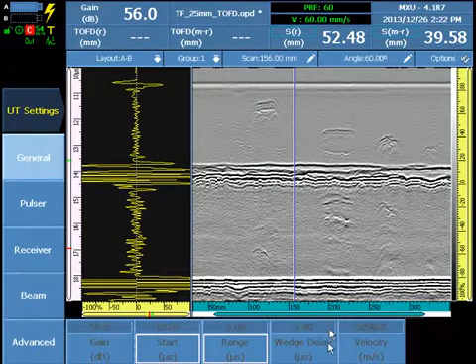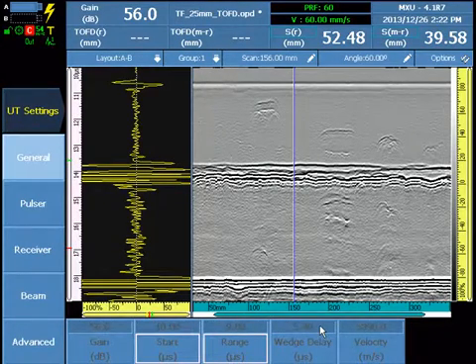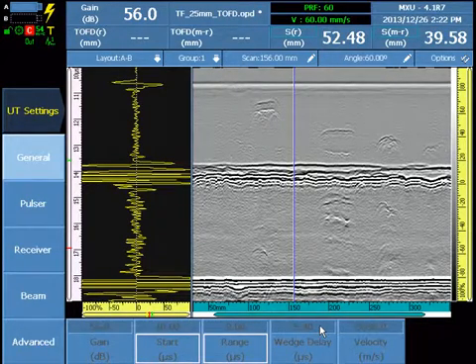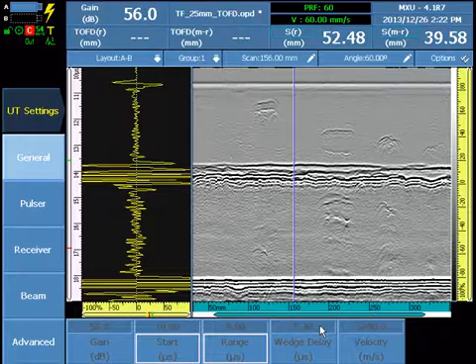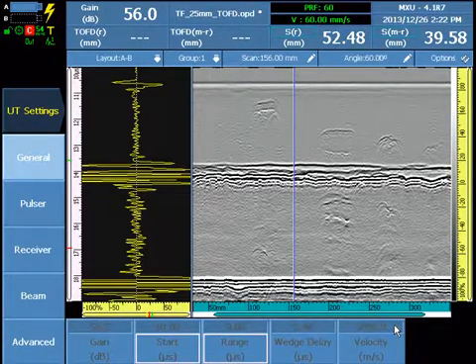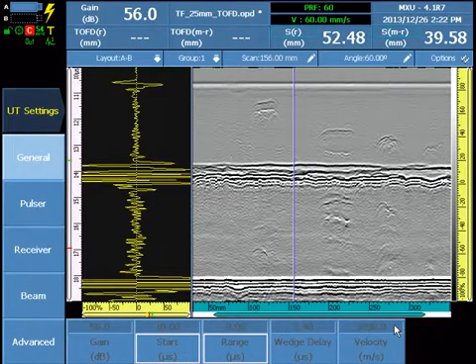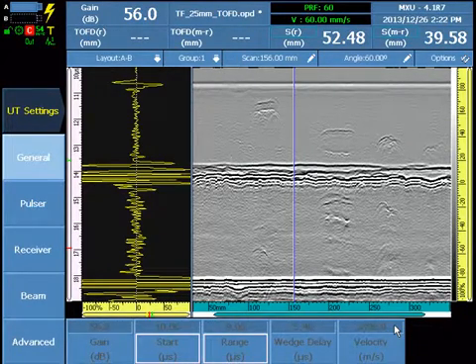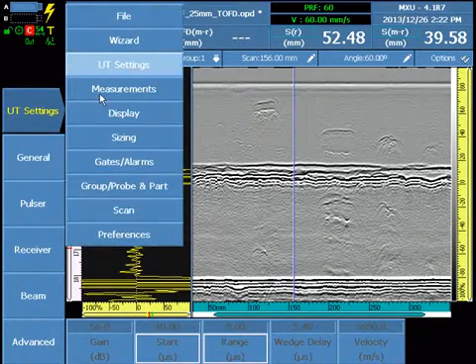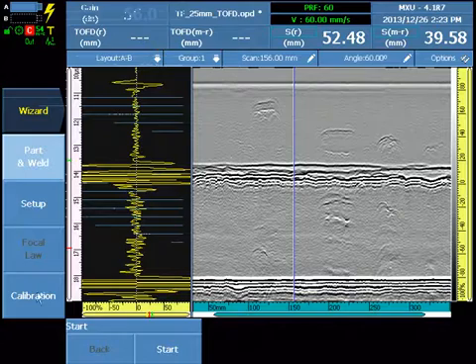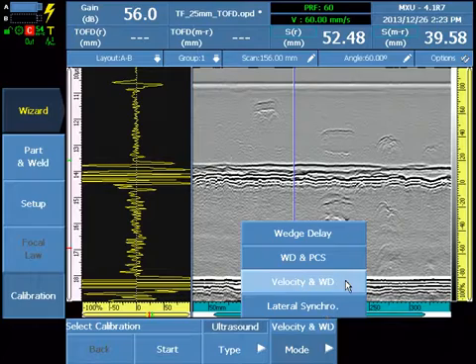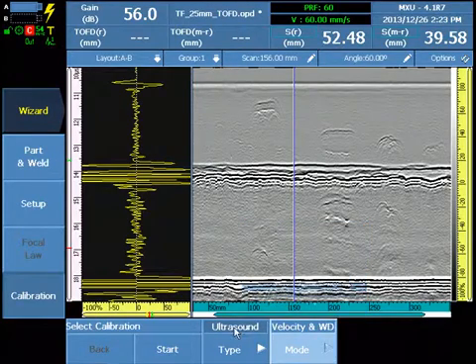During the course of the setup, the TOFD probe was selected from the database and a default value of 5.40 for the wedge delay was entered. The velocity of 5890 meters per second was used for the group setup and for data acquisition. To calibrate for wedge delay and velocity, enter the wizard and select type ultrasound and calibrate for velocity and wedge delay.